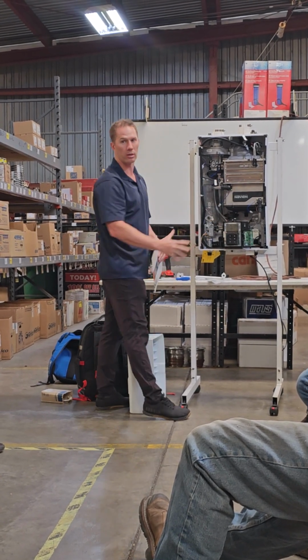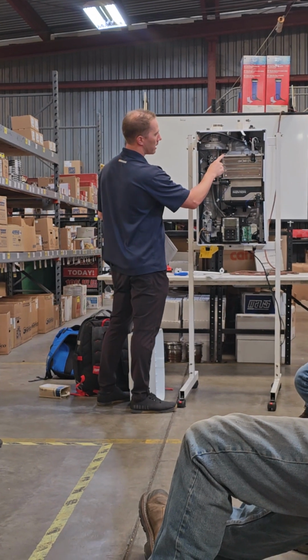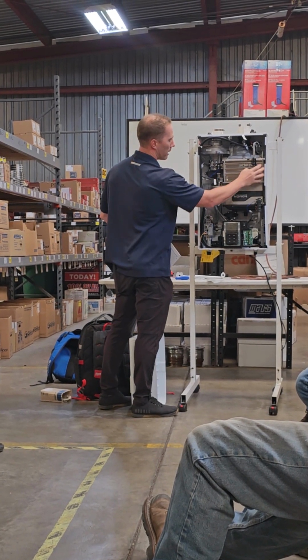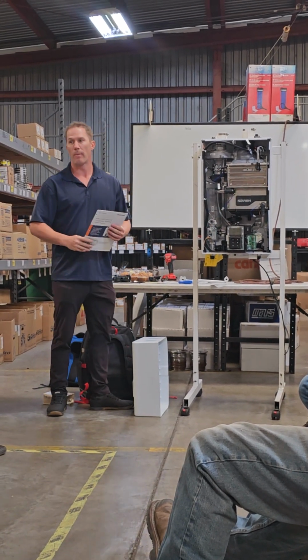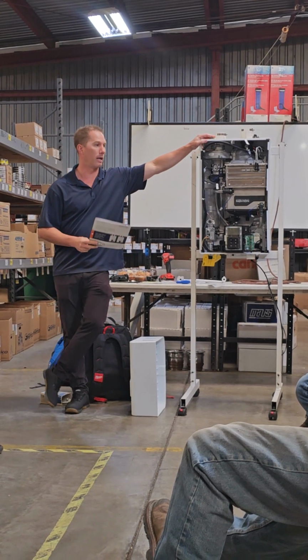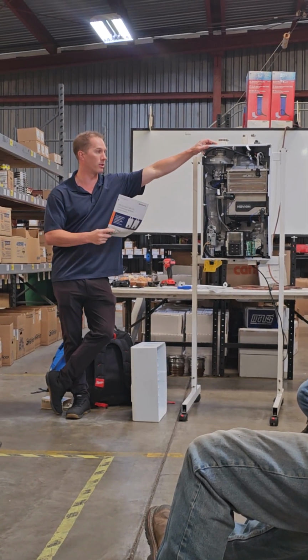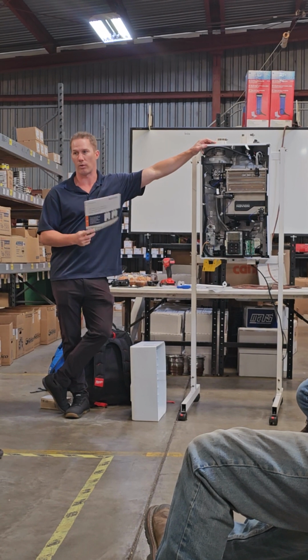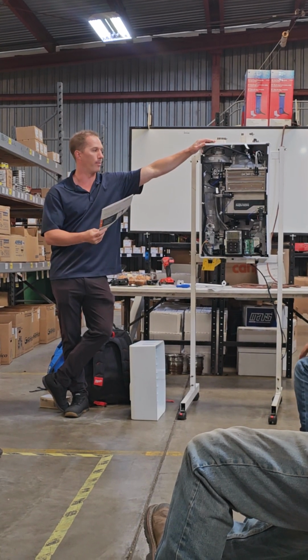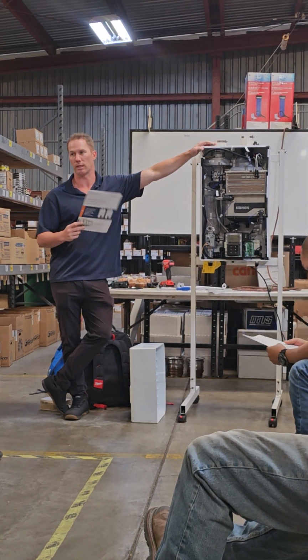And literally burns a hole in the heat exchanger. Then the heat exchanger will start leaking. So if you come to a heat exchanger where there's white stuff on the outside and it's crusty and it's leaking, I guarantee, 100% sure, that it's got hard water at the install and it burnt a hole in the heat exchanger. The heat exchanger is leaking.